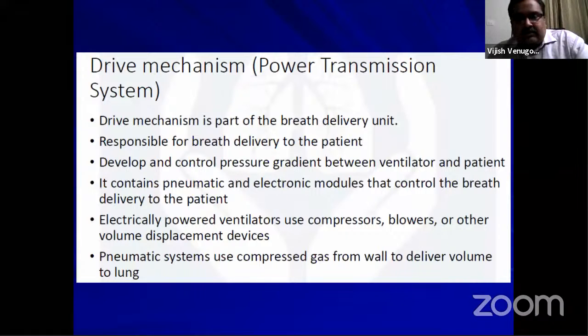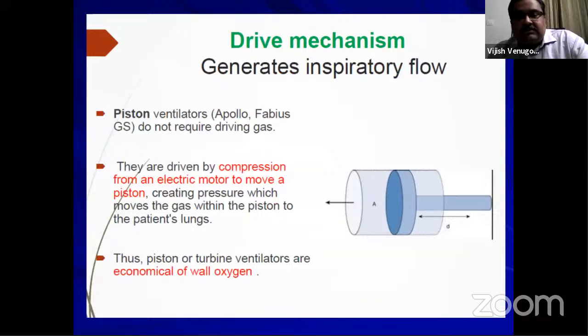So one type of drive mechanism is piston ventilators. Now these piston ventilators do not require driving gas. They are driven by compression from an electric motor to move a piston, as shown in this picture here. And the piston just pushes and it creates pressure which moves gas within the piston to the patient's lung.